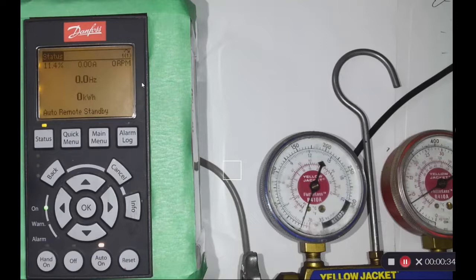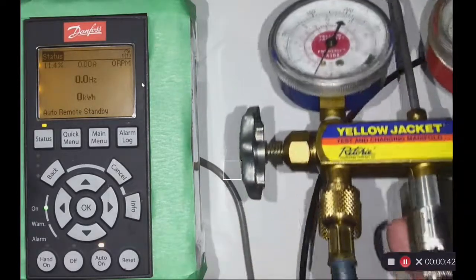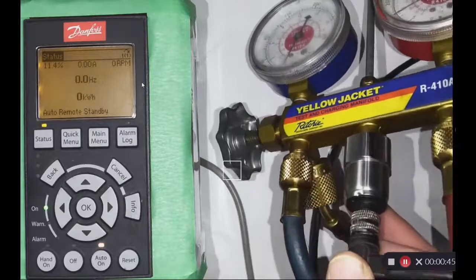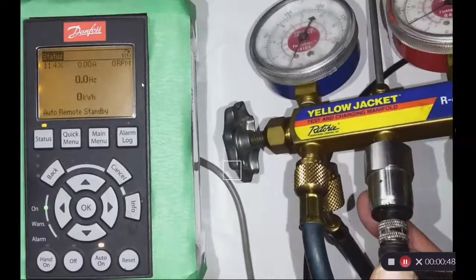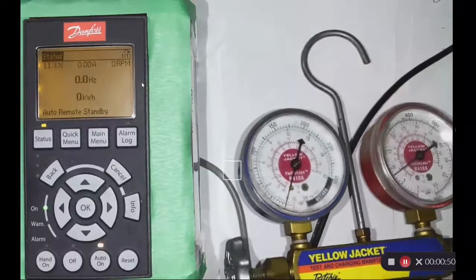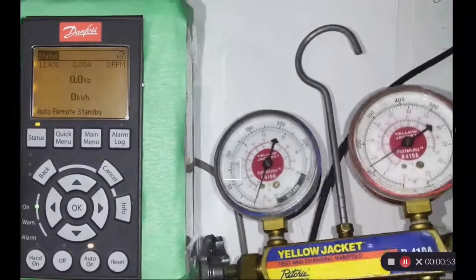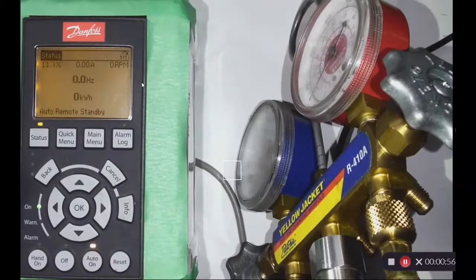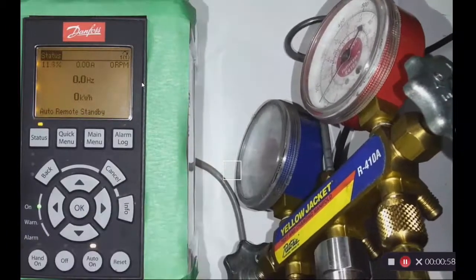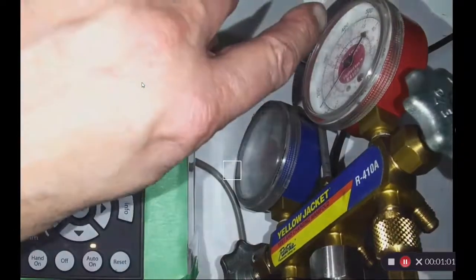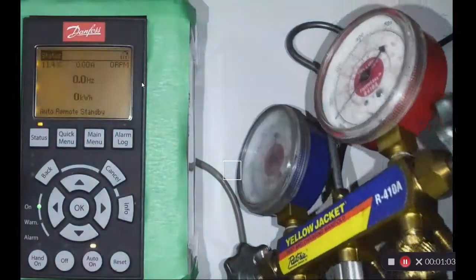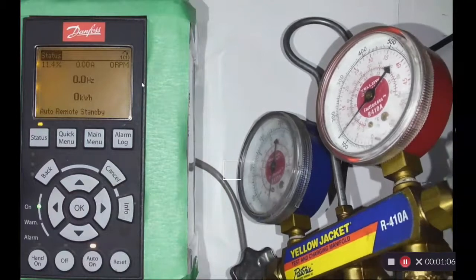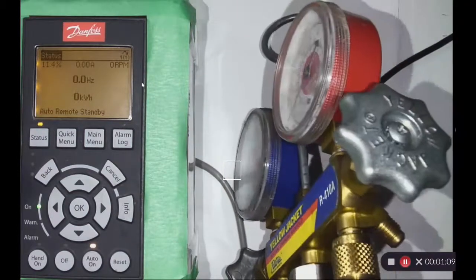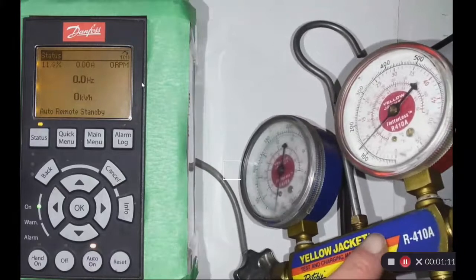I have a set of refrigeration gauges as well, and I've got my pressure transducer screwed into the center port, which you can't see. Well, I'll just move it. And it's onto the center port of our refrigeration gauges. And if you don't know how they work, it's not a complicated thing. There's two hand valves, and this one in red on the right-hand side goes straight through to the gauge, and you can see that I've got over 100 pounds of pressure from my nitrogen bottle. And there's a tap on the right-hand side which opens up a port right here inside.